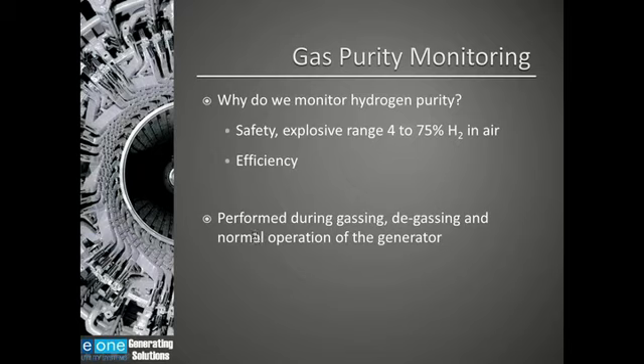These are some methods of monitoring gas purity. A manometer, which I'll say was used in the olden days, was a glass U-shaped tube filled with mercury. What this did is it measured a differential pressure, the high pressure and the low pressure. And the OEM, the generator manufacturer, supplied a graph with the generator, and you could take this differential pressure and convert it into purity. Then later there came a device, a gas density balance, which also measures differential pressure. And again, we take that differential pressure and convert it into gas purity.